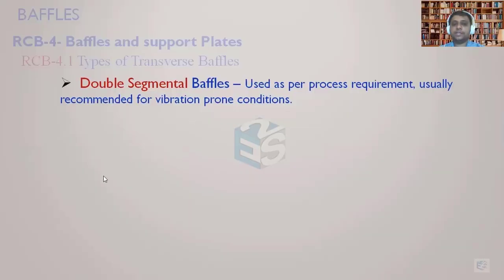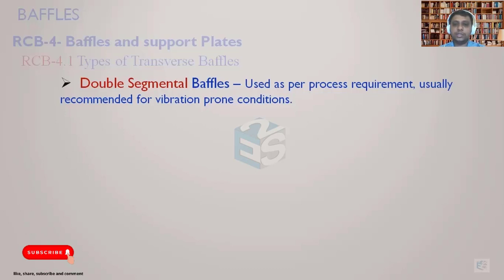Now the double segmental baffles. Single segmental baffles we have seen — there are three types of cut: horizontal, vertical, and the rotated one. Double segmental baffles are used as a process requirement, usually recommended for vibration-prone conditions. This is decided by the process based upon process requirements, residence time, and if vibration is observed — to reduce or remove that vibration. They might go for double segmental or triple segmental baffles. In steam applications where high velocities are present, double or triple segmental baffles are provided if the steam is on the shell side, along with an impingement plate.